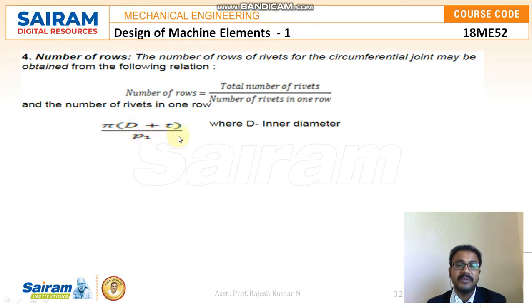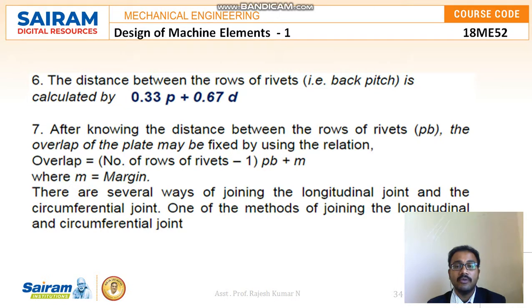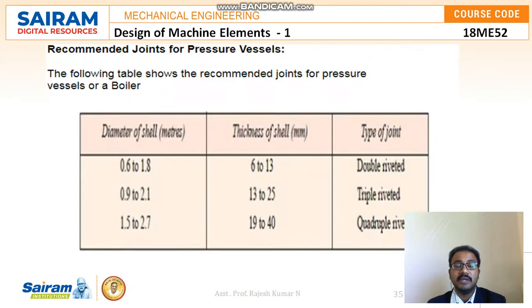By using this formula we find the inner diameter indirectly. After finding the number of rows and the type of joint — whether single riveted or double riveted — the number of rivets in each row may be re-adjusted. To ensure a leak proof joint, the pitch should be checked from Indian boiler regulations, where the value 2 is replaced with 1.875. The back pitch (distance between rows) is calculated as 0.33P + 0.67D. The overlap of the plate is fixed using the relation: (number of rows - 1) × Pb + M, where M is the margin.